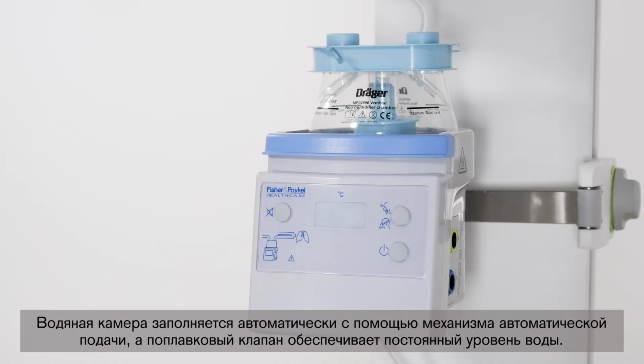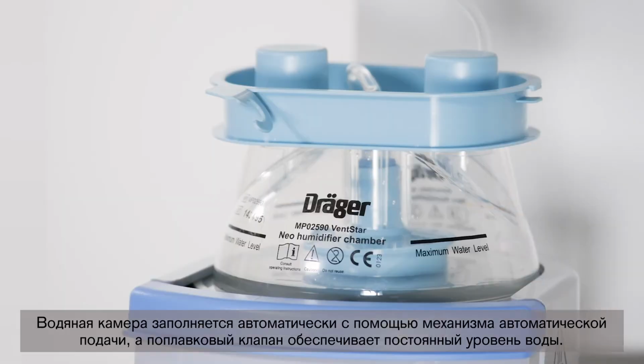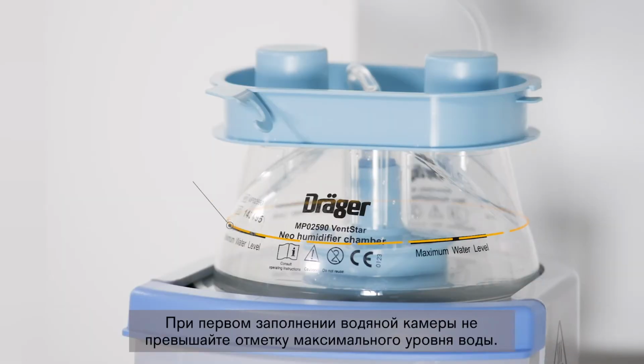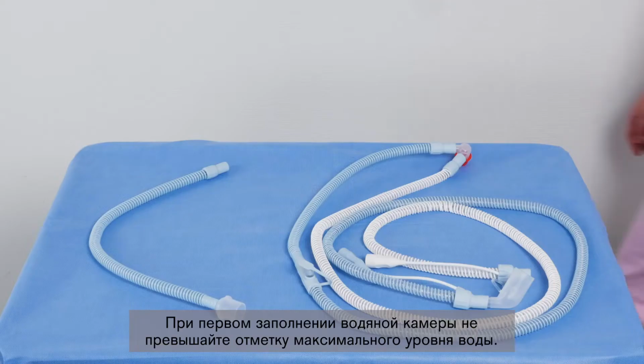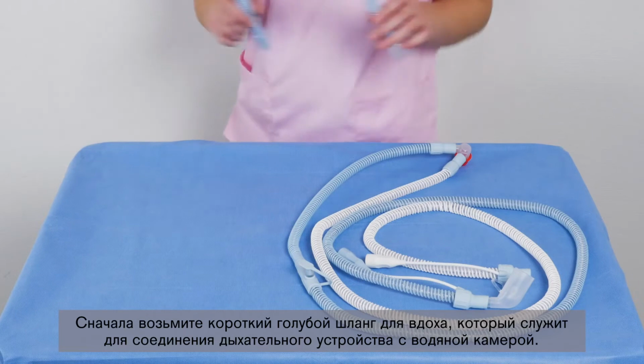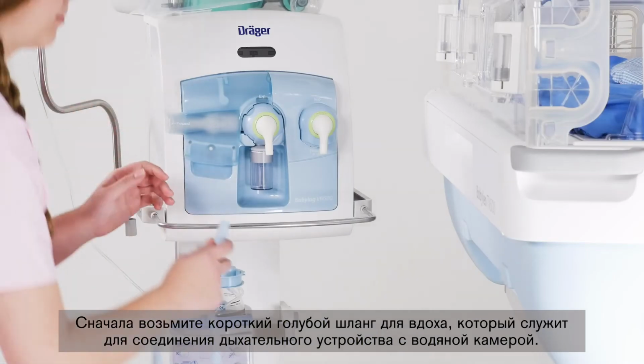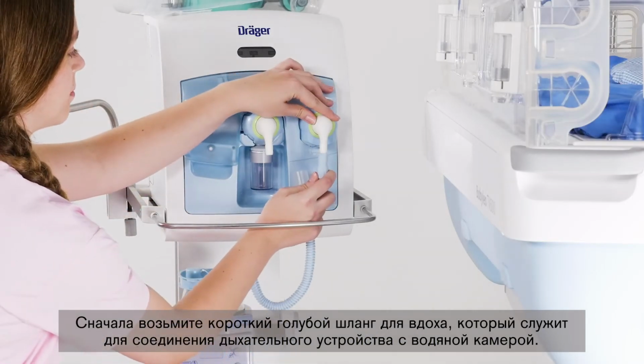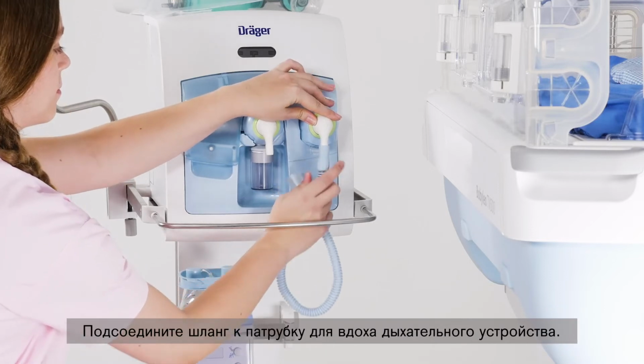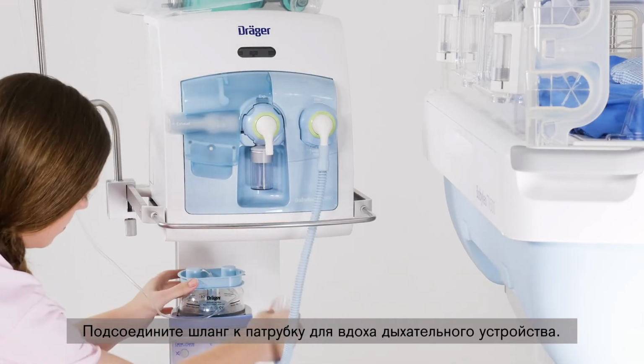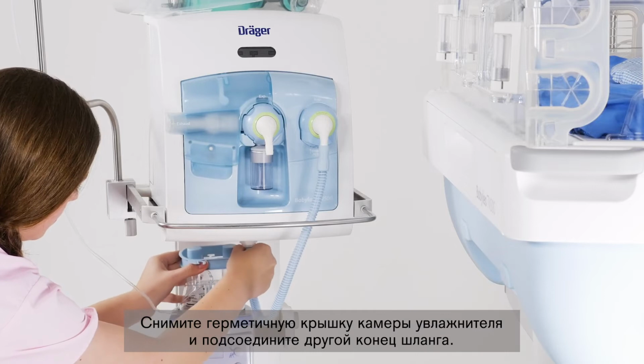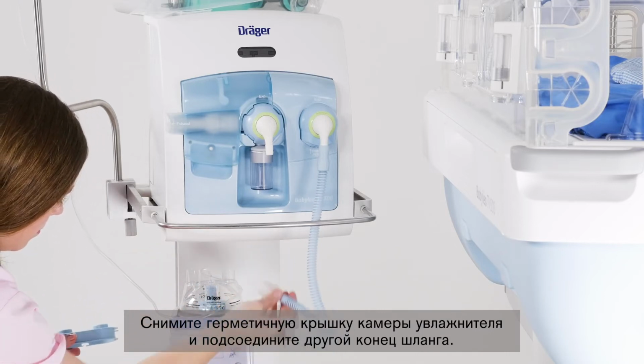The water chamber is filled automatically by means of the auto feed mechanism, and a float gauge ensures that the water level remains constant. The first time the water chamber is filled, be sure not to go beyond the maximum water level mark. First, take the short blue inspiration hose, which serves to connect the breathing device to the water chamber. Connect the hose to the inspiration nozzle of the breathing device. Remove the sealing cap of the humidifier chamber and connect the other end of the hose.